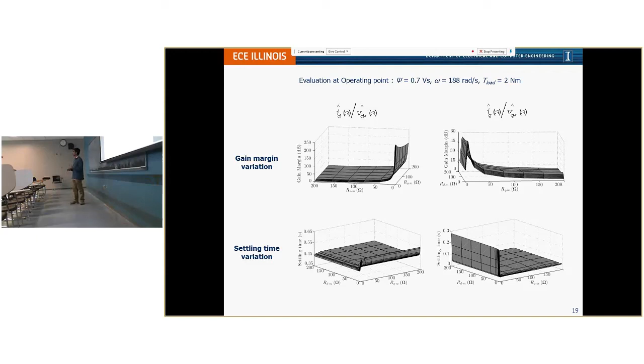The damping controller is turned on only at 0.25 seconds. Before that, you see that because of the lack of damping, the resonant oscillations are very bad. Once the damping is introduced, we get rid of the harmonic components, and there is only the fundamental available in both the voltages and currents. Similarly, the rotor speed was not really subject to much oscillation before—it's a very small amplitude—but the torque oscillation is very bad, bipolar, shooting up and down, which is not good because of the currents. So the active damping controller has been proved to be effective.